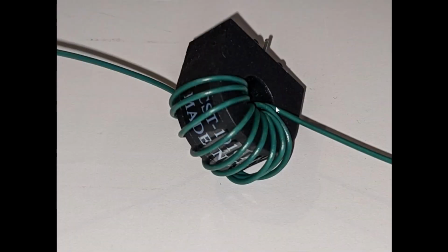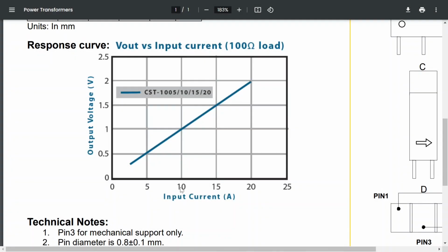To increase the ability to measure small currents and simplify the math, I've run a wire through the aperture of this transformer 10 times, so 1 amp of current will now appear as 10 amps as far as this transformer is concerned. So rather than a 10 amp to 1 volt ratio, our device will now have a 1 amp to 1 volt ratio.